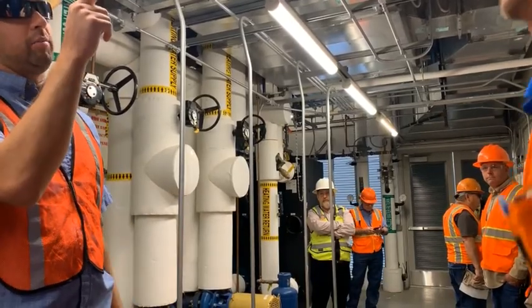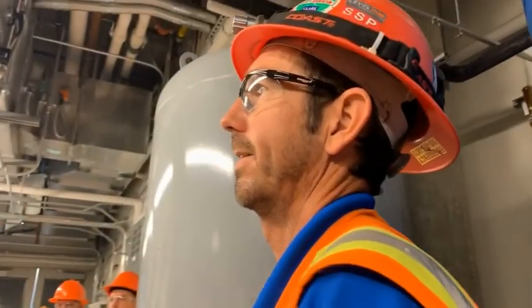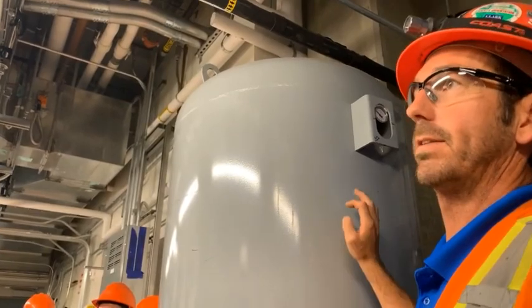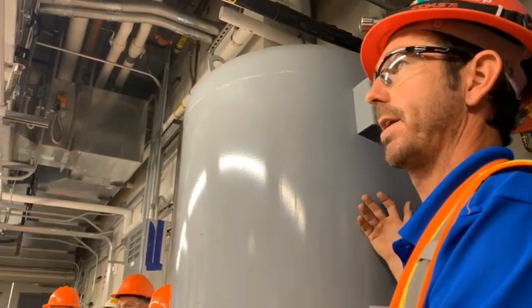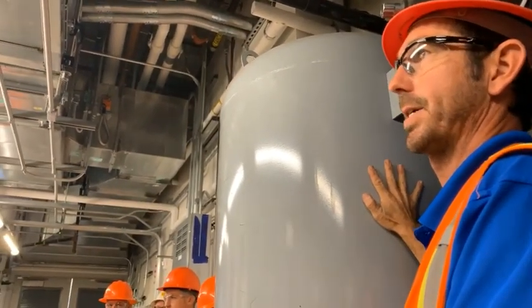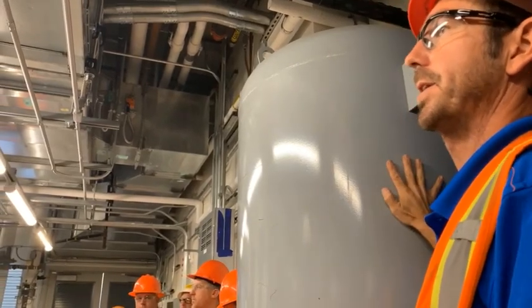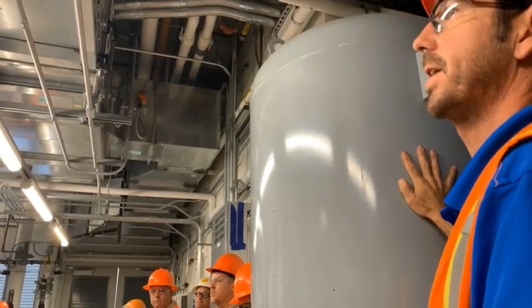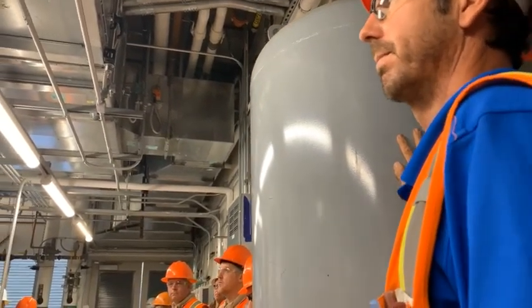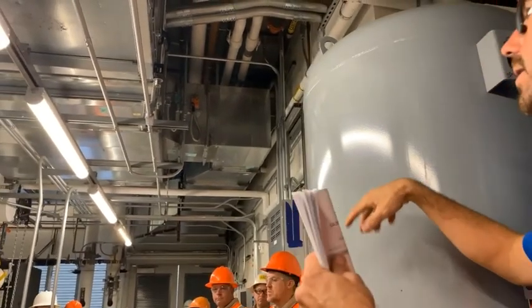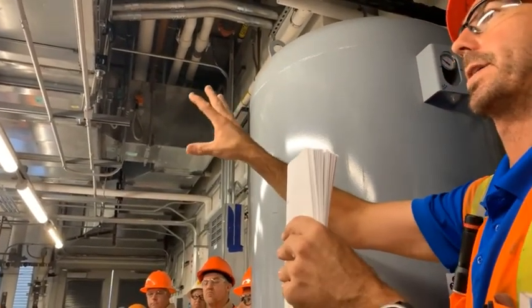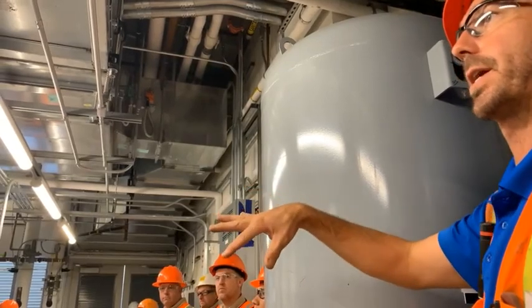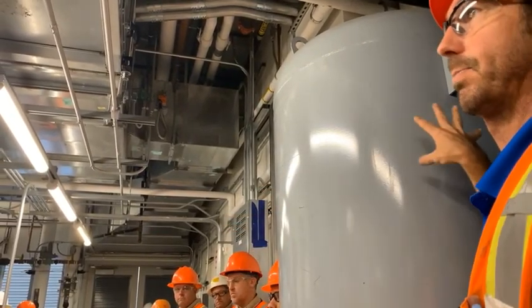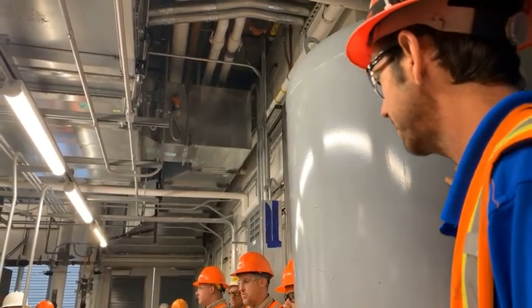And now that pressure gauge right there reads it all the time? Yeah, but it's the system pressure, not just the bladder pressure. Okay. To check the bladder pressure, you have to shut it off and drain it. Yep. And then you could check that. Yep. Okay. Because right now it's open to the system, and whatever that pressure is, I mean, it is the suction pressure, right, but that's pushing into the tank. Right. Cool.